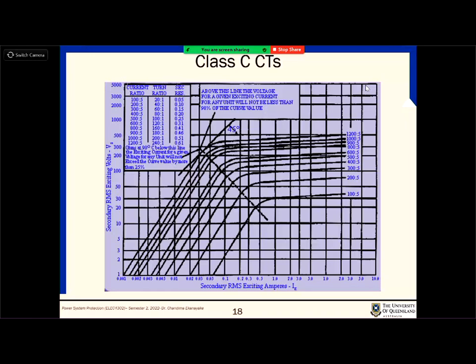And then there is a small table in the top left-hand corner that gives you, for different turns ratios, the secondary resistance of the CT. Because every CT has a certain number of windings. Those windings will give you impedance. Therefore, the secondary resistance is also quite important to look at. Got it? So when we do the calculations, we will look at the secondary resistance as well.